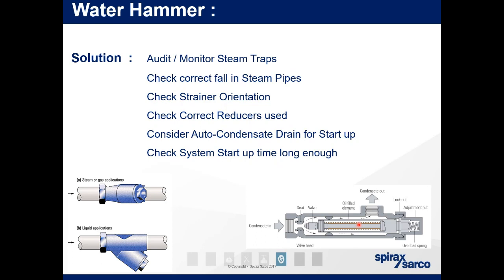You then could see the same kind of damage on control valves. So if you have water hammer on a control valve, you can damage the stem seals. So you'll see leaking from the stem coming from the bonnet. You can damage the seat itself. By having a control valve, you can also introduce water hammer if you have condensate in your system.